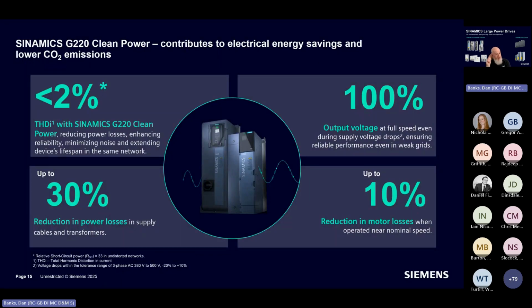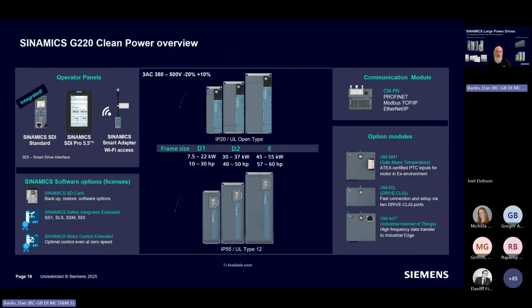Again, just to highlight: 2% THDI, 100% output voltage at full speed, including voltage dip ride through, because it's an active front end, so it can do boosting of input to output voltage. That's going to reduce the losses in your surrounding system from the harmonics by up to 30%, which I don't think is the headline - it's really about that maintenance piece of cutting down the heat and keeping your equipment reliable, and potentially reducing the losses in your motor from running a cleaner supply.